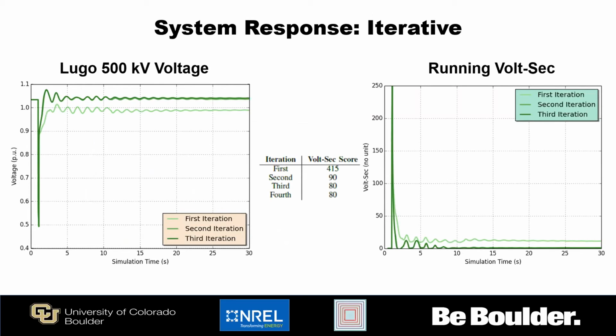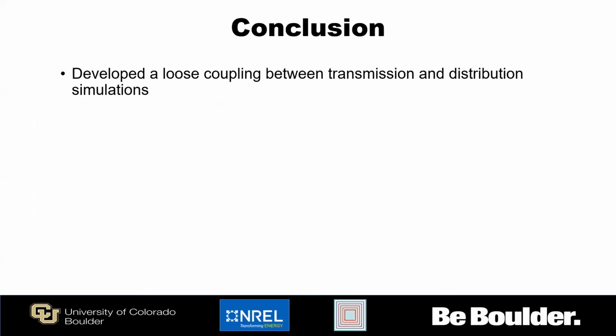So the voltage profile also looks quite a bit improved as we iterate through and can take corrective actions. So we see reduced volt-second scores going from about 415 all the way down to 80. And you can see how that impacts the voltage near the fault location as well as the volt-second scores.